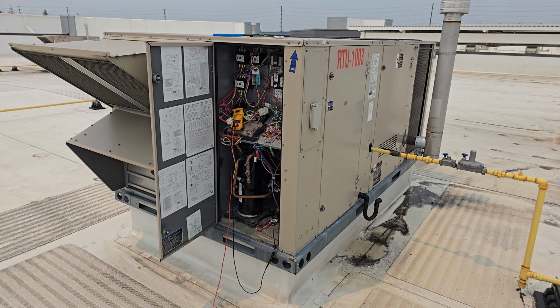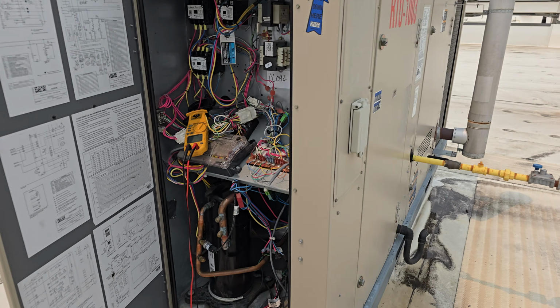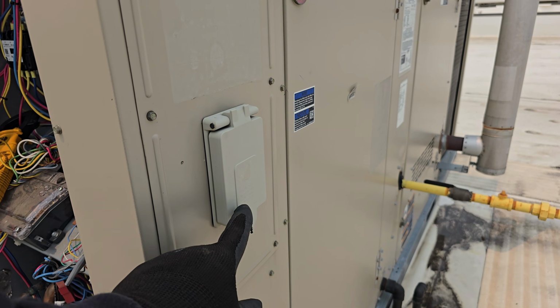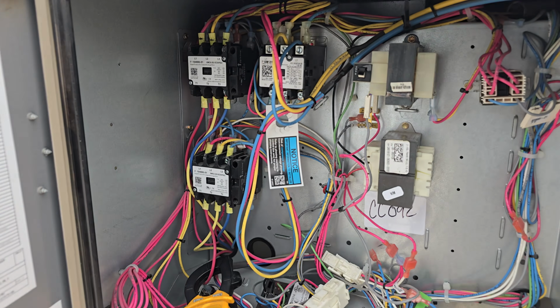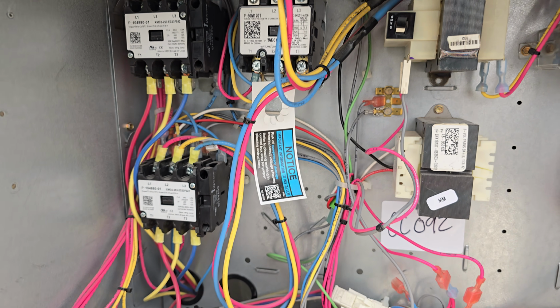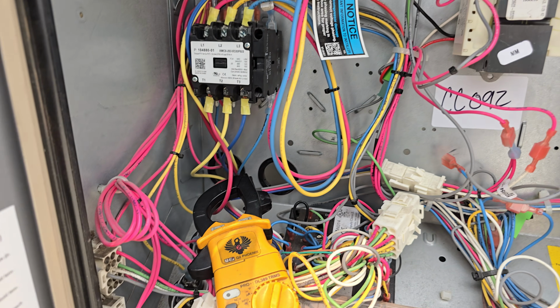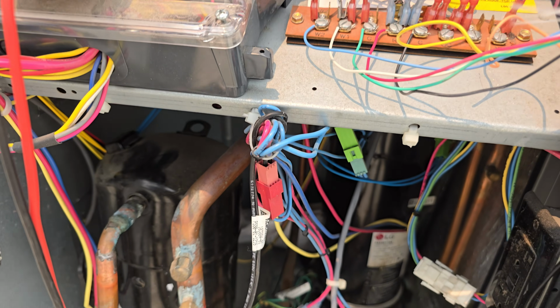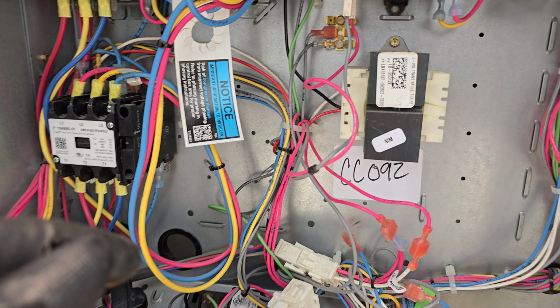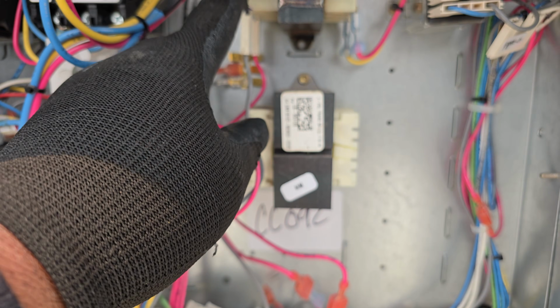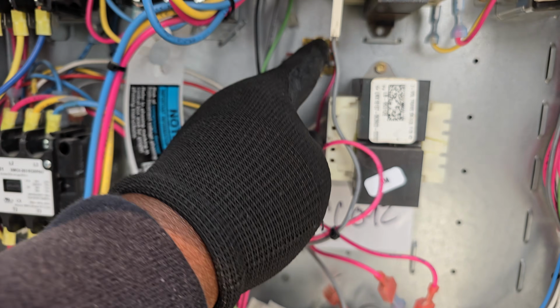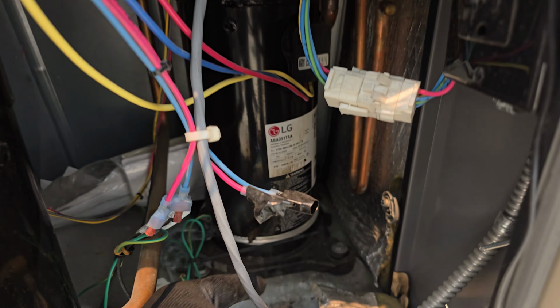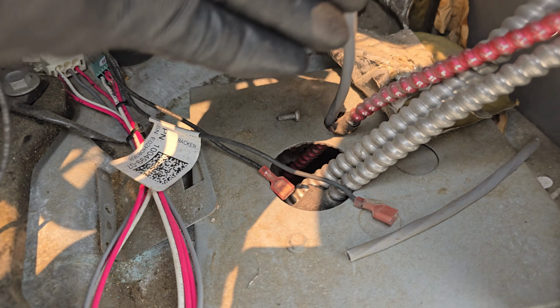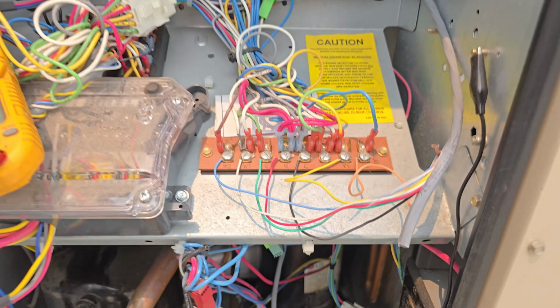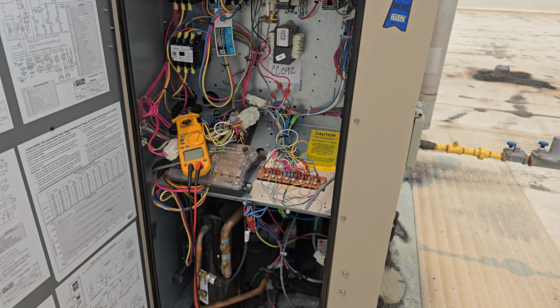Okay, with my HVAC turned off, the main power turned off here, I want to start by checking whether any 24 volt is going to ground. I'm going to reset this guy. I'm going to check and see where there is any wire going to ground, especially the low voltage coming from the ground here. I'm going to do a lot of checking and inspection here.